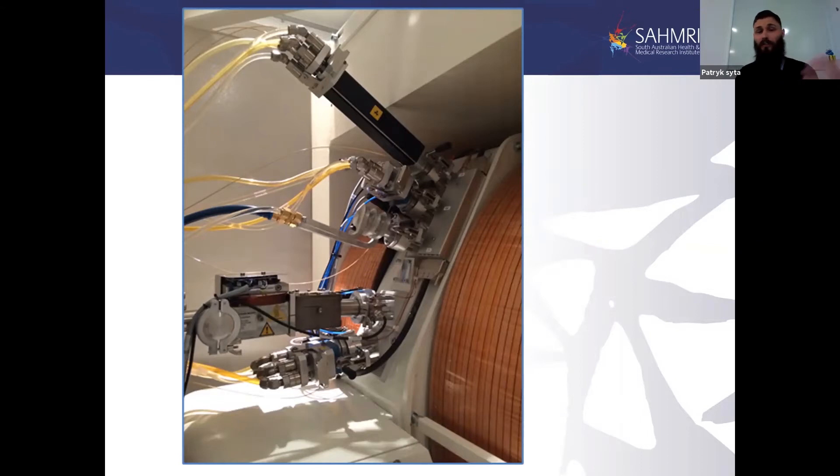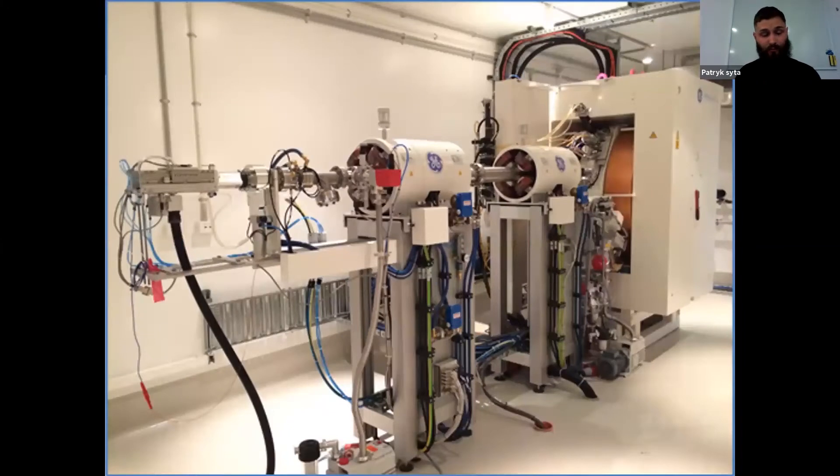We design the types of feedstock — the preliminary isotopes and the ones that they will transmute into — to produce the desired radiological decay that we will exploit for these purposes. The cyclotron we have here is able to bombard liquid, solid and gas targets, with our mainstay being the production of F-18 through bombardment of O-18 water. However, our largest opportunities are centred around our solid targetry and our beamline capabilities. This is one of the few cyclotrons that has the capability for both solid targetry and beamline in Australia, and we are currently some of the best producers of radioisotopes in that regard.